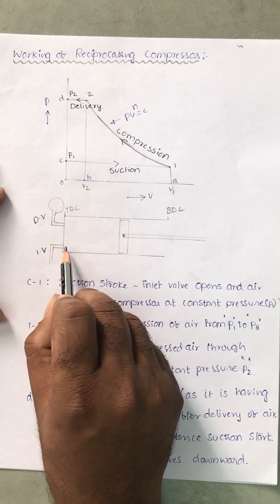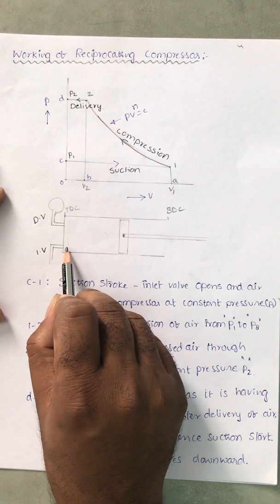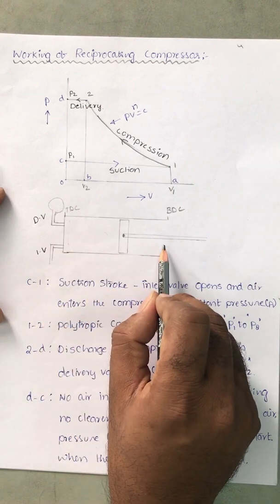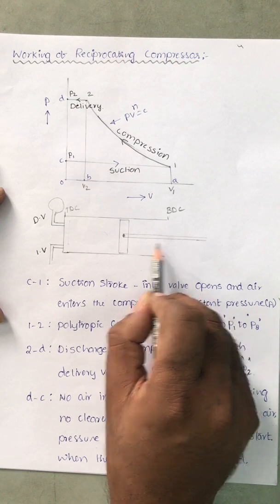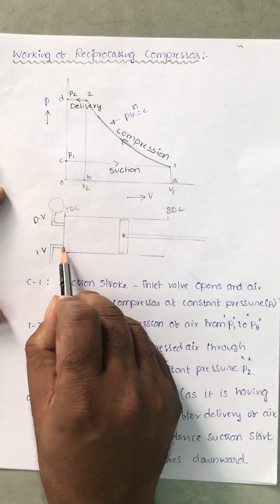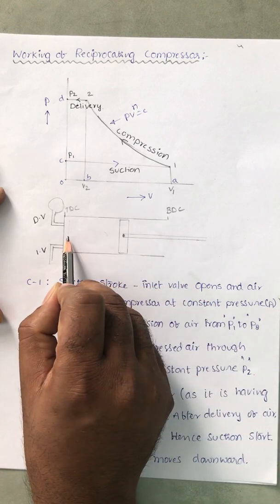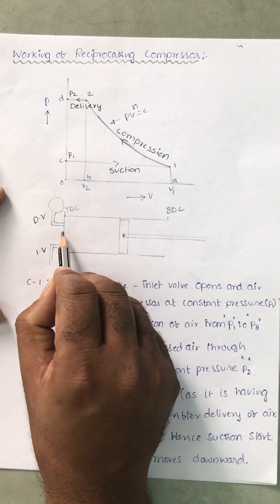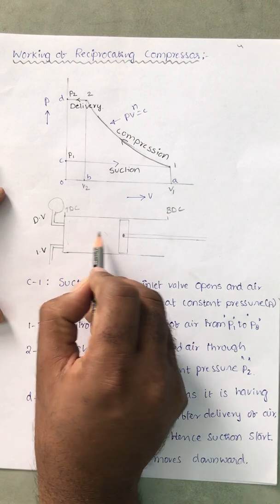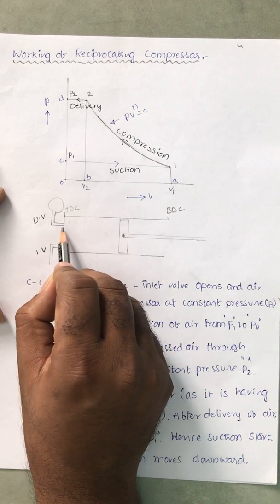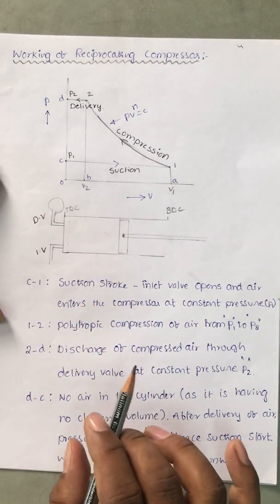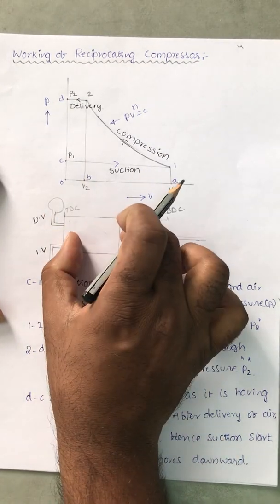The next cycle is then repeated. The inlet valve remains open until the piston reaches the bottom dead center — that is the suction stroke. When the piston starts to move upward from the bottom dead center, the inlet valve closes and compression takes place until the piston reaches the top dead center. The delivery valve remains closed until it reaches the top dead center, then the delivery valve opens and this air under high pressure is sent to the container. This is the cycle of operation.